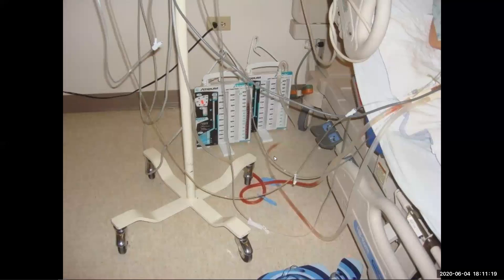All right. So here on the Atrium, this is the collection chamber. That's where that blood's going to collect. You can measure it. This is your water seal, and this is your pressure regulating here. The water seal is for us to manage and monitor this device. It also tells us, is our stuff working? I should see some gentle fluctuations with each respiratory cycle, not sloshing up and sucking, but a little gentle back and forth. And if I see some gentle bubbling, that's okay also. I don't want to see boiling. I don't want to see rolling, frothing stuff in here. Gentle bubbling, slight fluctuations, it's working fine.